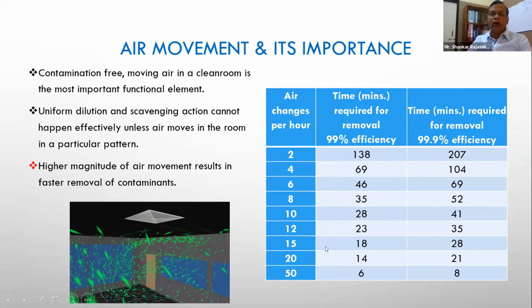So this is what you are likely to look at. In a surgical procedure, we are likely to have anywhere between about 18 to 20 minutes between two surgical procedures, or at the maximum say about half an hour. We are somewhere in this band. Between 14 to 28 minutes is normally the time these days we get between two procedures. And you look at the time that is required for a 99% removal, and the theater to come back to its steady condition of aseptic nature takes something like about 20 minutes.